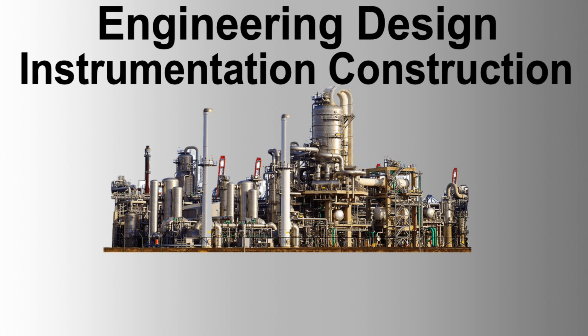Control valves shall normally be provided with block valves and a bypass valve. However, a bypass shall not be provided for control valves for safety shutoff or depressurizing service, and on some applications where solids suspended in the stream may collect and block the bypass valve. The block valves on either side of the control valve shall be of the straight-through type and of the same size as the piping. The bypass valve shall have a nominal capacity factor at least equal to, but not more than twice, the capacity factor of the control valve. The bypass valve shall have a good throttling characteristic.